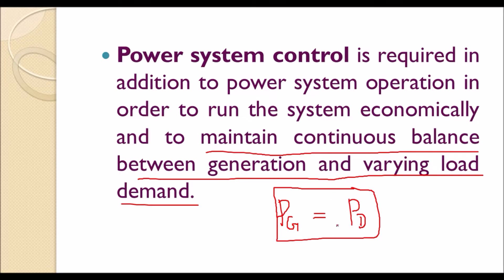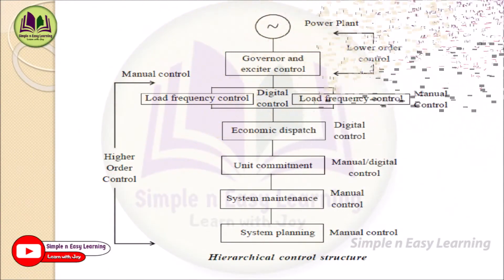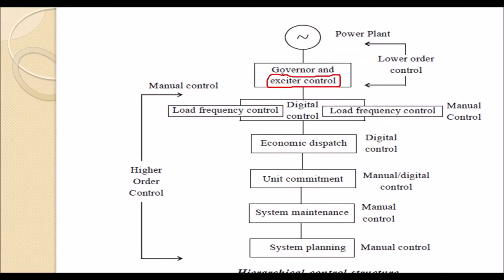The power balance equation — generation equals demand — requires power system control. The main control operations are frequency control and voltage control. These form a hierarchical control structure. A power plant has a governor and exciter control mechanisms. The exciter controls the excitation of the generator by varying field current, thereby controlling voltage. The governor performs speed control: if frequency changes, the speed is adjusted to bring frequency back to its normal value.